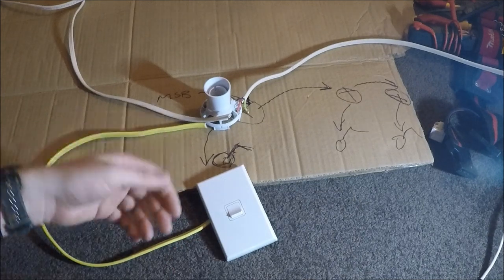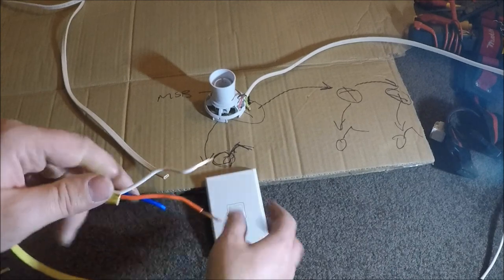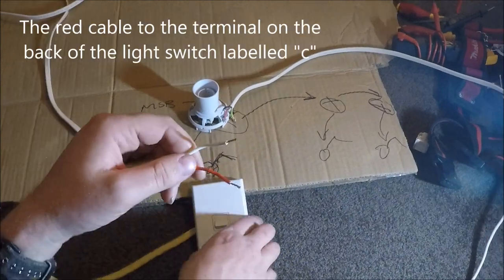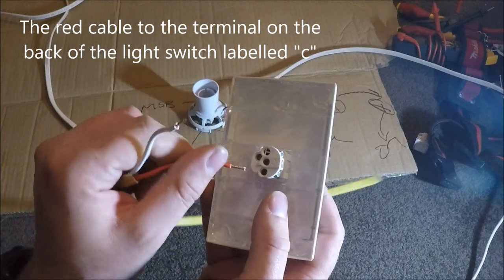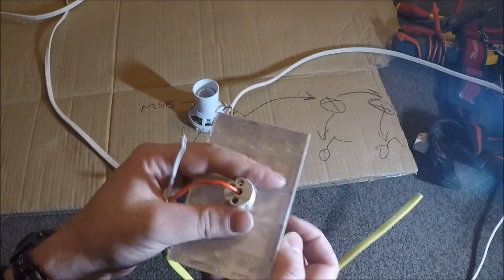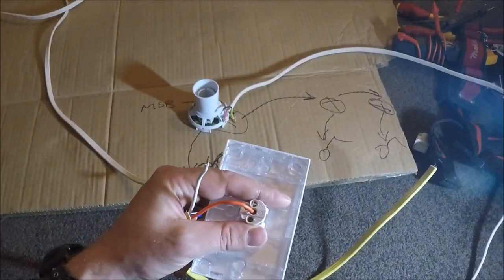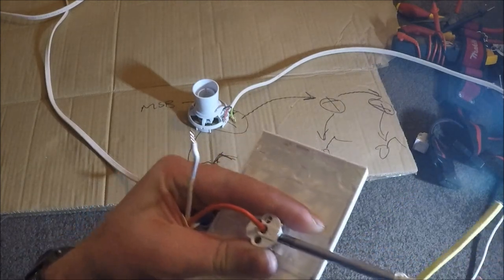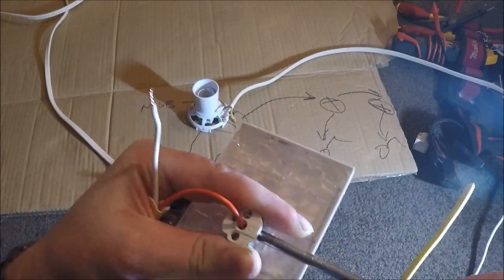Now the way you wire these, I'll start with the light switch. So we only need to use two cores. We'll be using red and white, and we'll put the blue one in the connector. So at the light switch here, we're going to wire the red into C, and this red will be connected up to the feed that goes to the switchboard. So the C is always from the switchboard, and the number one behind the light switch is always the one going to your light fitting.